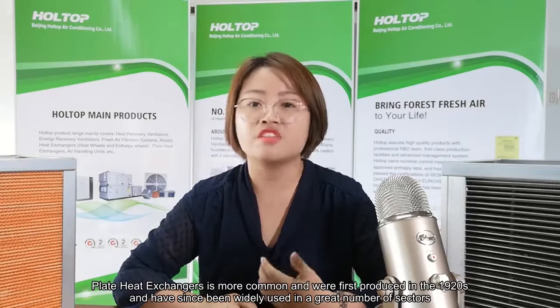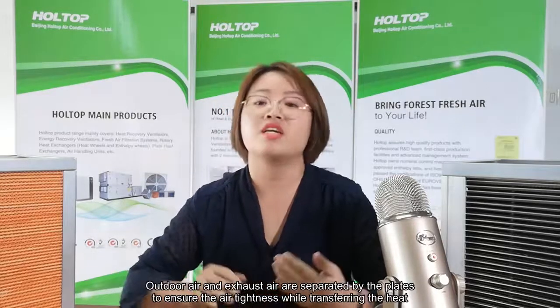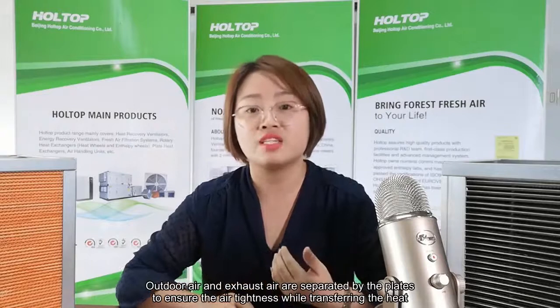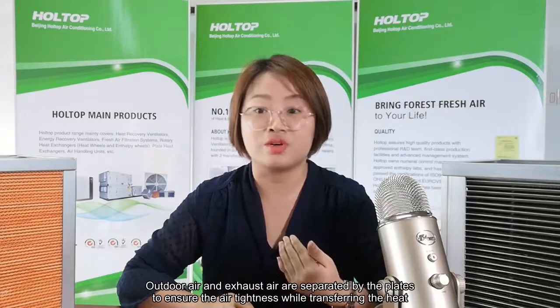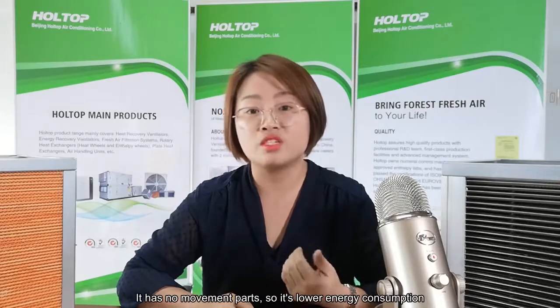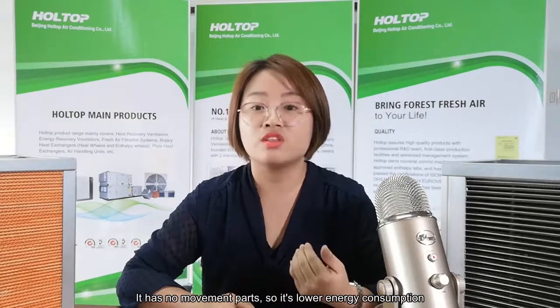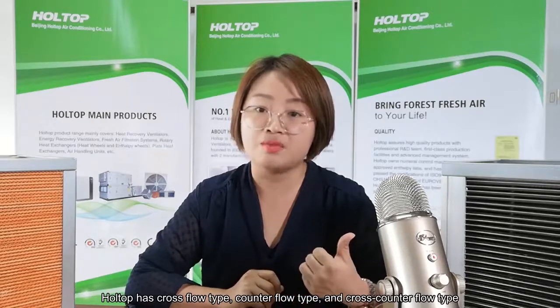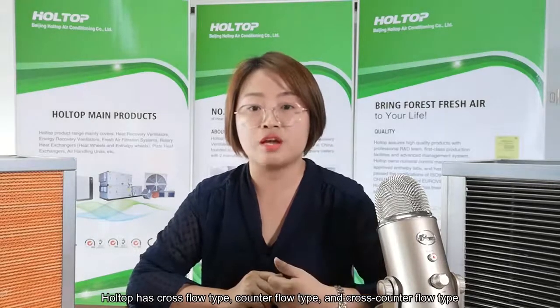Type 2 is plate heat exchangers. Plate heat exchangers are more common, were first produced in the 1920s, and have since been widely used in a great number of sectors. Here we only talk about the air-to-air heat exchanger. The outdoor air and the exhaust air are separated by the plates to ensure air tightness while transferring the heat. It has no moving parts, so it has lower energy consumption. According to the airflow directions of the heat exchanger, Holtop has cross-flow type, counterflow type, and cross-counterflow type.